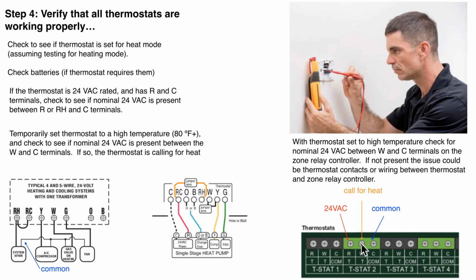If there's a call for heat coming into this thermostat, you would have a nominal 24 volts between common and W. If you don't have that voltage there, maybe the wire's broken, maybe something in the thermostat is broken. We've seen sheetrock screws driven right through thermostat cables that would short it out and keep basically the call for heat on perpetually. So basically we're looking for, starting at the thermostat, do we have a legitimate call for heat, and is that call making it down to our zone relay panel?